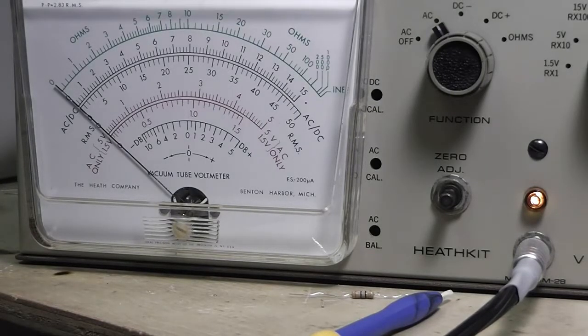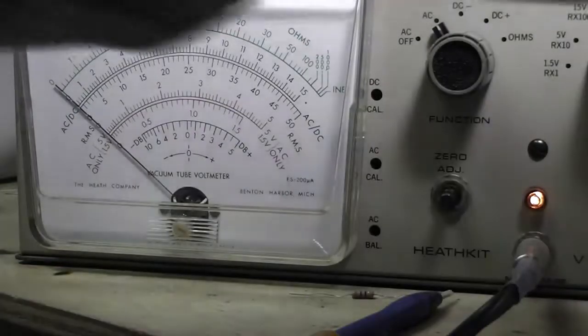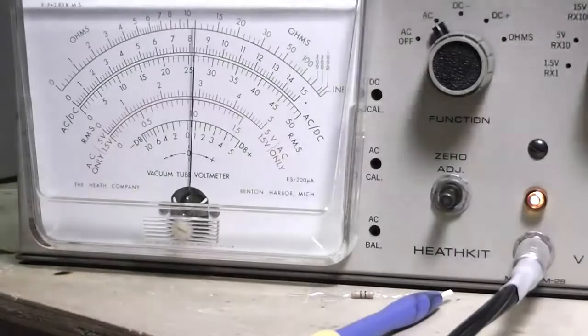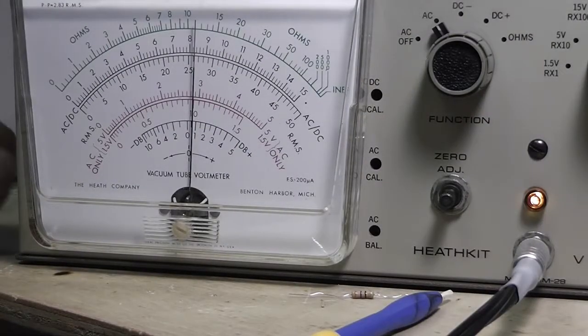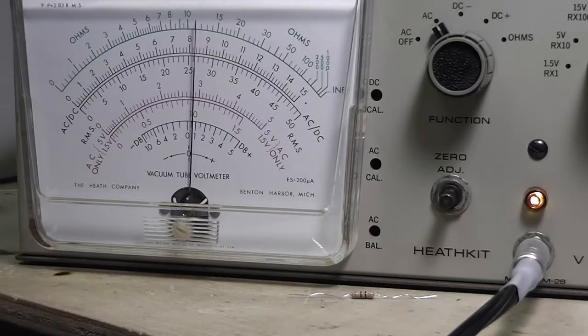And then it says connect the test probe to the side of the AC line with the highest reading. Adjust the AC calibration control until the meter pointer indicates the line voltage. Okay, so I've got this one set. So we should only need, since it's grounded, we should only need this one. We shouldn't need both. Okay, I plugged it in the AC side there. Be very careful doing this. And I've got it plugged into a Variac that I've got set with another meter to read 120 volts. Our line voltage here is about 122.3 to whatever. It kind of fluctuates, but anyway, go into the AC calibration here.